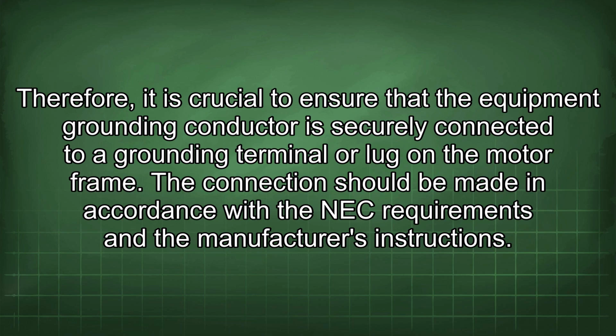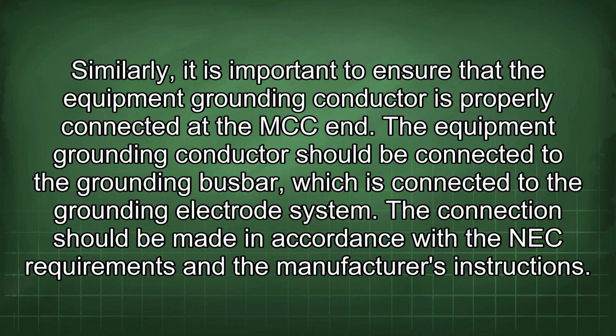Therefore, it is crucial to ensure that the equipment grounding conductor is securely connected to a grounding terminal or lug on the motor frame. The connection should be made in accordance with the NEC requirements and the manufacturer's instructions. Similarly, it is important to ensure that the equipment grounding conductor is properly connected at the MCC end. The equipment grounding conductor should be connected to the grounding busbar, which is connected to the grounding electrode system. The connection should be made in accordance with the NEC requirements and the manufacturer's instructions.